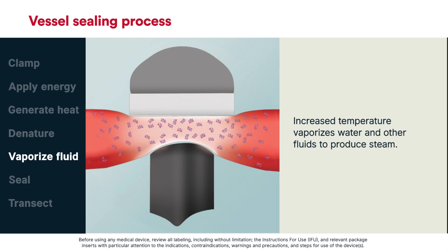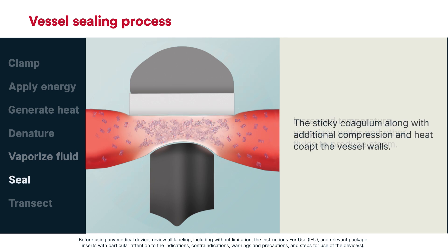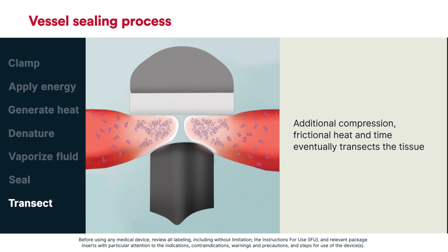The increased temperature vaporizes water and other tissue fluids to produce steam. The denatured proteins form a sticky coagulum, and along with additional compression and heat, the opposing vessel walls co-apt to form a seal. Additional compression, frictional heat, and time eventually transects the tissue.